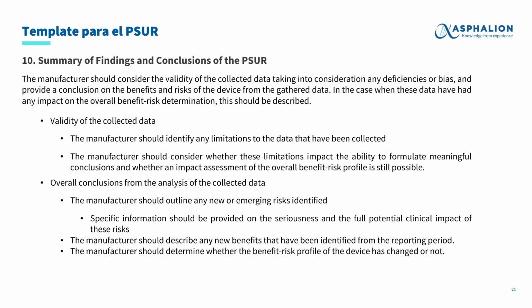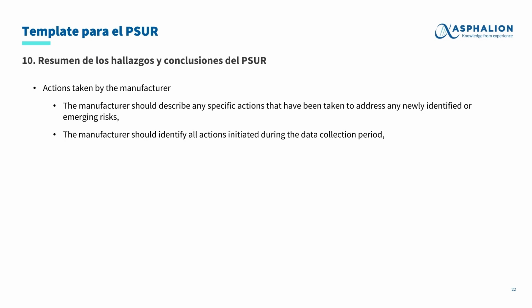The manufacturer should also outline any new or emerging risk identified during the reporting period, providing information on the seriousness and full potential clinical impact of these risks. The manufacturer should also describe any new benefit identified during the reporting period, and obviously a conclusion regarding the benefit risk profile of the device, if it has been changed or not, and in case of change, if this change is positive or negative for the safety of the device. And finally, a description of all actions taken by the manufacturer during the reporting period to address any new identified or emerging risks. So all these sections that we have seen here today are at least the sections that a PSUR for a medical device must include to be in line with the requirements stated in the medical device regulation.